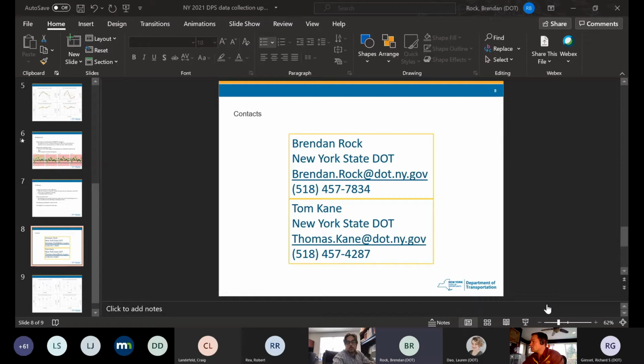I'm going to lean on Tom a little bit because he was actively involved at the time we did these things. So we've got both of us here. So the sensor was 6 inches off. Yes, obviously we're cutting our core right. A lot of these, I believe, were wedge joints, so we were right along the wedge for the actual core, but the sensor was 6 inches off. Okay, so that could explain some of the difference between what the DPS was predicting and what the core was showing. And I should say some of the slides that Brendan shared really highlighted some of the things that we're seeing, but we had other locations where everything lined up really, really close. There just seemed to be a little bit more variability when looking at all of the data from the joints.